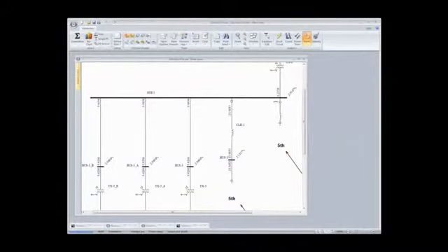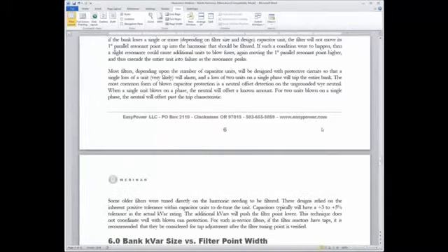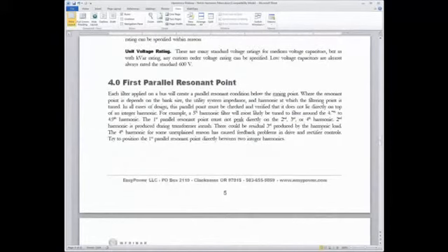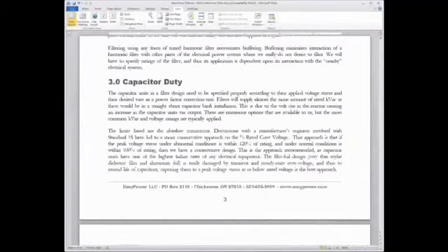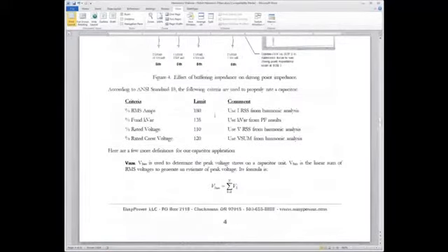Yes, if you look in my notes, I probably said I had not updated that. In my notes, I think I noted 180 or something like that. I must have accidentally deleted that out. Thanks, John, very much for that update. So I'll change this for everyone for the RMS amps to 135%.